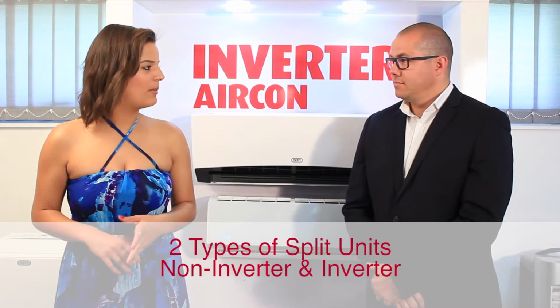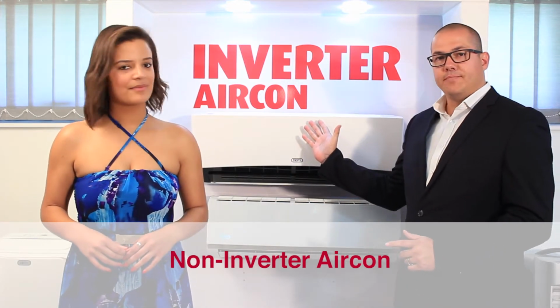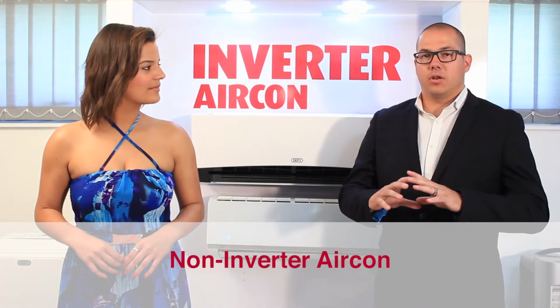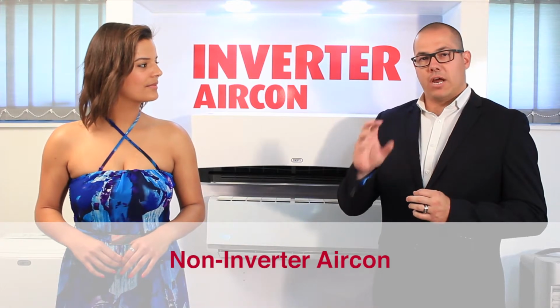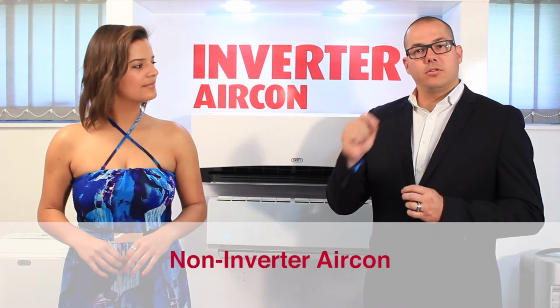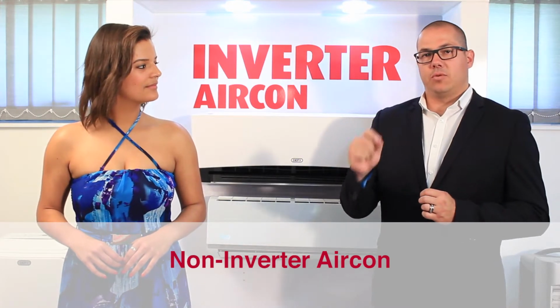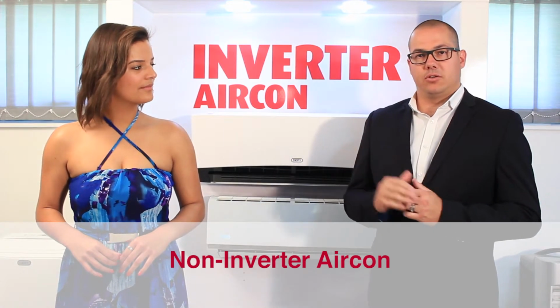Can you explain a bit more about the difference between the two? Yeah, so if you look at your non-inverter, if you put it in a bedroom and you set it on 22 degrees, the unit will run until 22 degrees and it will switch off. Then it will pick up 2 degrees in temperature to 24 degrees and the unit will switch on again to try and bring your temperature back to 22.